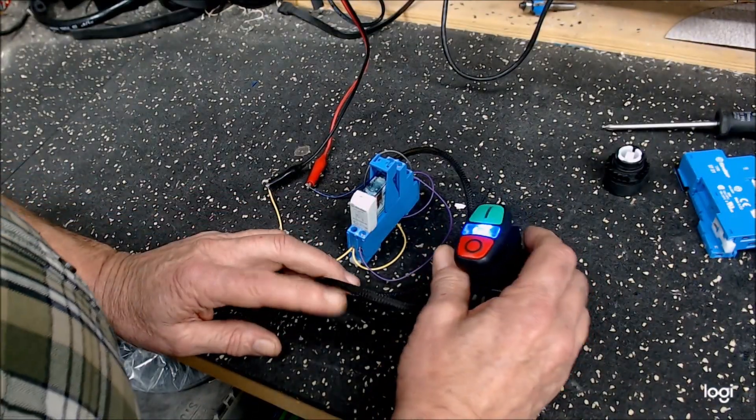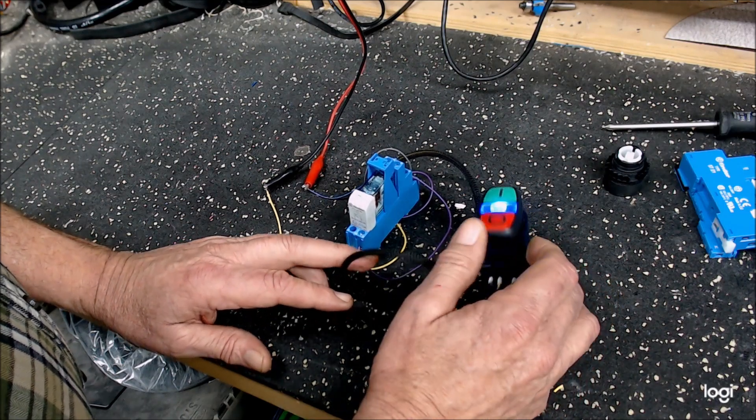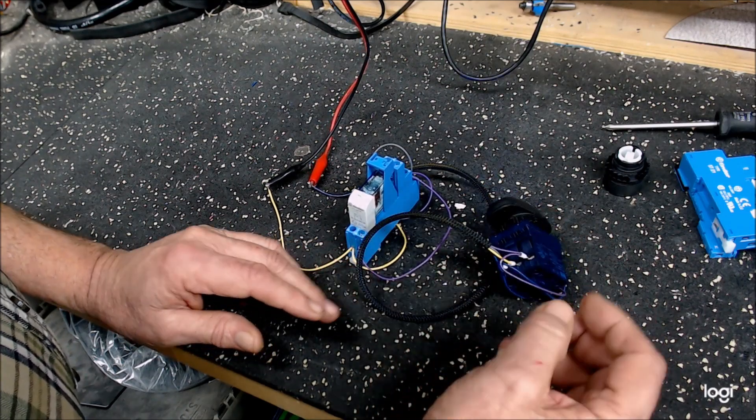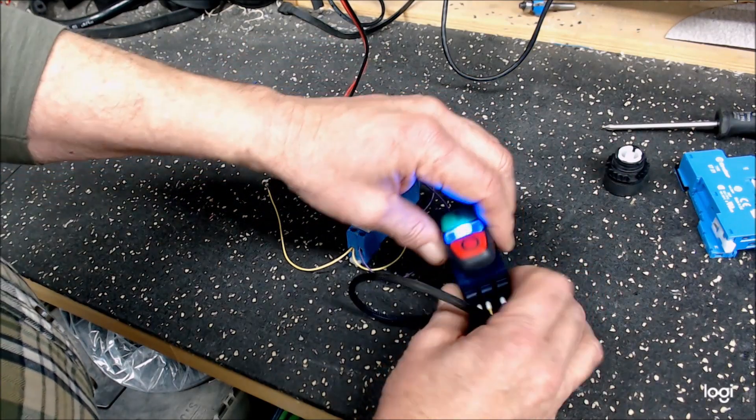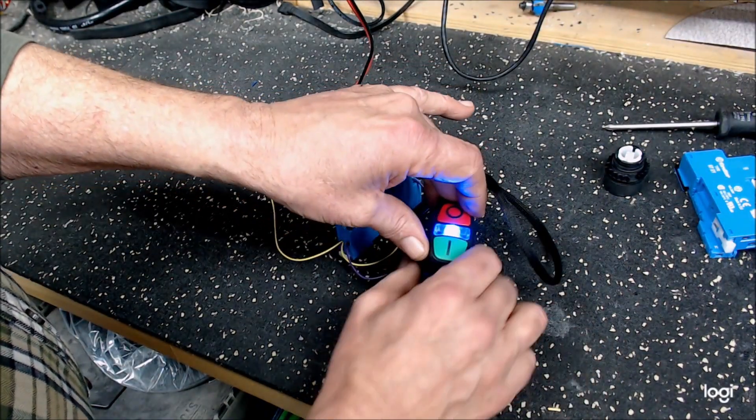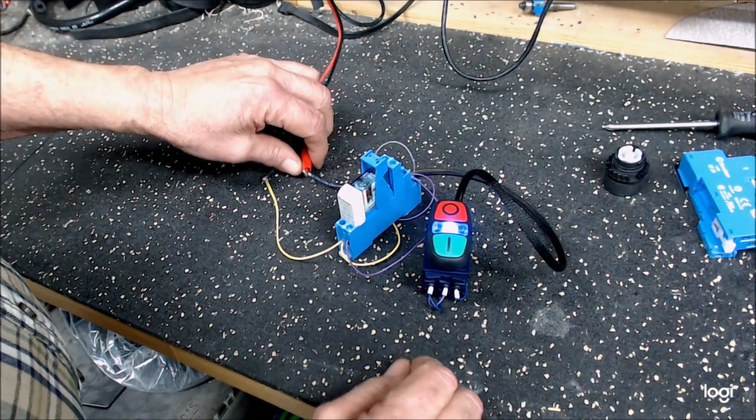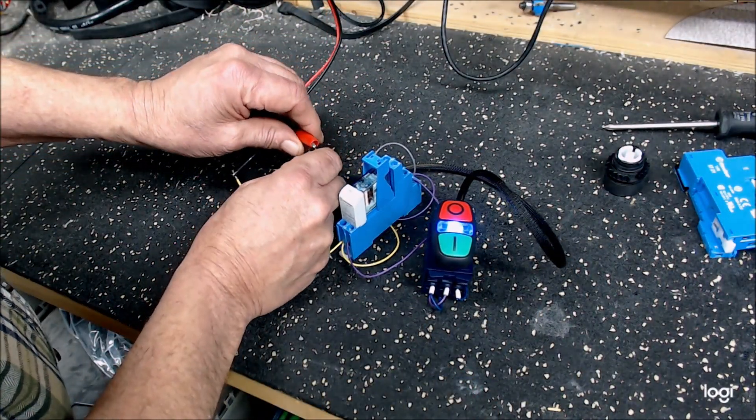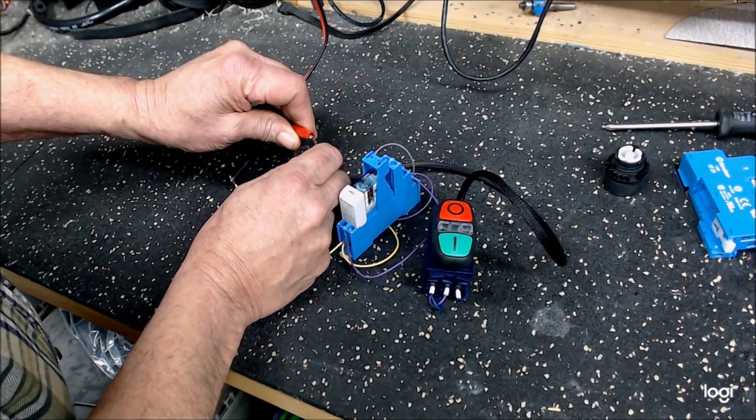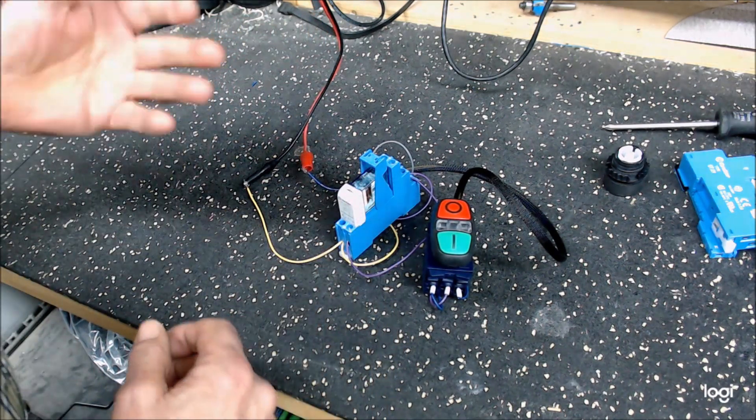Now the reason that you want to use these relay circuits is in case something you're controlling is a safety type device. Latching circuits are used in case there's an e-stop or a power shortage. I'm going to disconnect the power - there it goes off. If the power were to come back on, it will not energize.